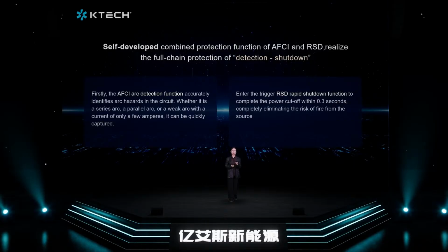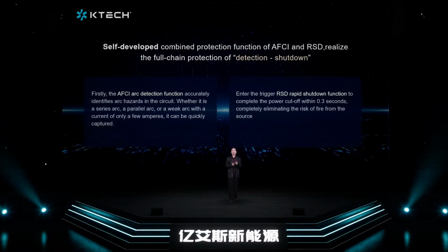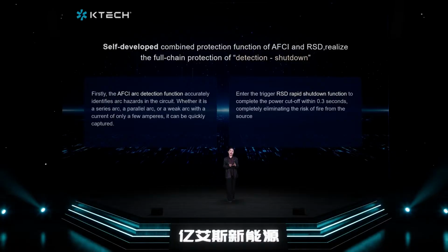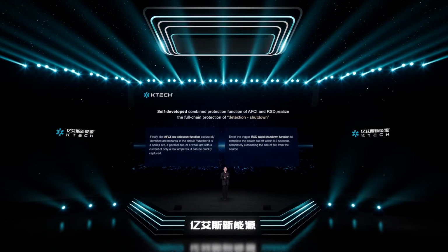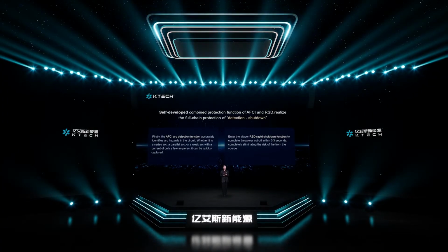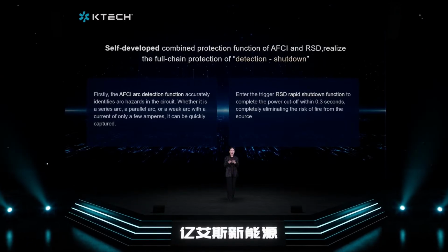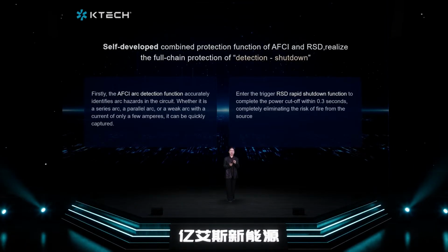Traditional inverter circuits cause hidden arcs, which conventional protection struggles to protect against. However, our combined protection captures arc risks via AFCI, then RSD cuts power in 0.3 seconds. Comparative tests show unprotected equipment ignites insulation in 3 seconds, while ours stops risks in 0.3 seconds to keep equipment and circuits intact. That's why manufacturing customers in America and Brazil said post-test, 'we must choose RSD and AFCI equipped equipment.